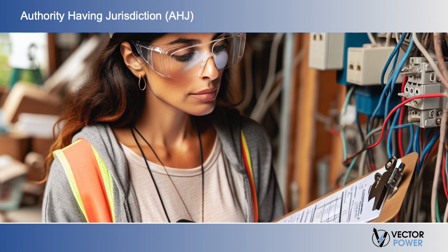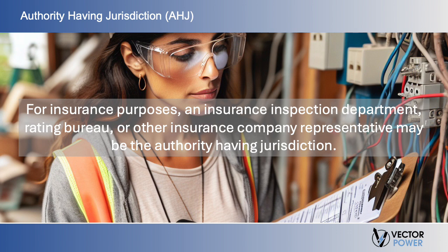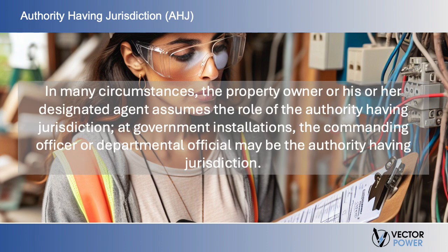It should be noted that the phrase authority having jurisdiction, or AHJ, is used in NFPA standards in a broad manner because jurisdictions and approval agencies vary, as do their responsibilities, where public safety is primary. The authority having jurisdiction may be a federal, state, local, or other regional department or individual such as a fire chief, fire marshal, chief of a fire prevention bureau, labor department or health department building official, electrical inspector, or others having statutory authority. For insurance purposes, an insurance inspection department, rating bureau, or other insurance company representative may be the authority having jurisdiction. In many circumstances, the property owner or his or her designated agent assumes the role of the authority having jurisdiction. At government installations, the commanding officer or departmental official may be the authority having jurisdiction.